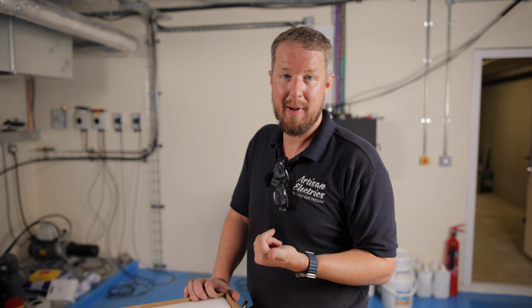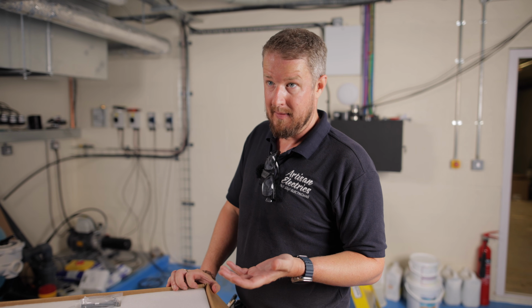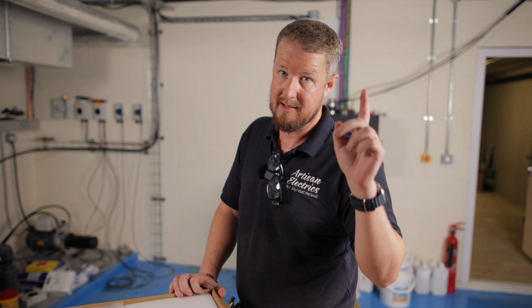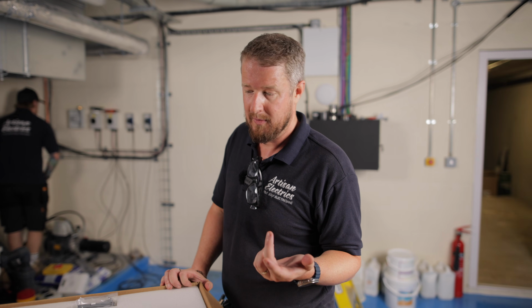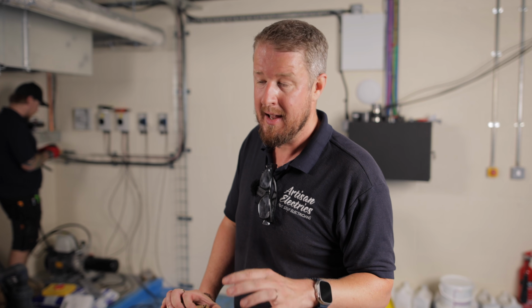But then this takes it to another level, because the Tesla Powerwall and the Sigenergy all-in-one, for example, are EPS, not UPS. That means they'll switch over to backup mode, but it takes a few milliseconds and they might skip like half a sine wave or something. So you can't guarantee that the supply will be uninterrupted - electronic devices might trip out and reset, for example. This is what they call UPS, uninterrupted power supply, which means it switches over within, wait for it, 0 milliseconds, and keeps the power running completely uninterrupted.